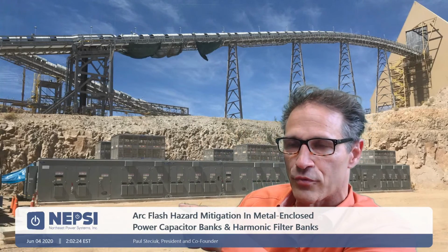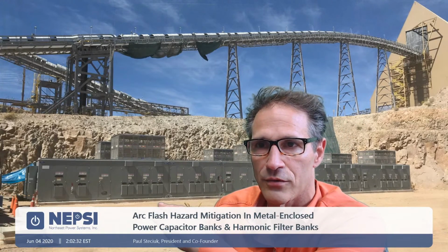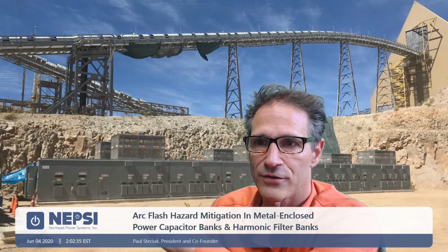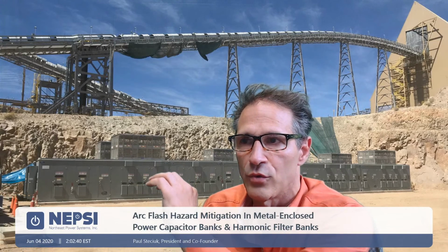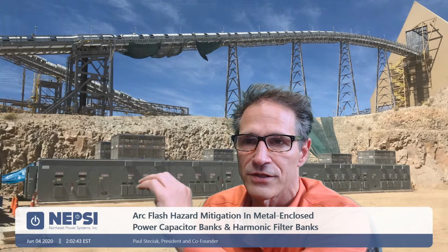So today we are going to be talking about arc flash hazard mitigation as it applies to metal enclosed harmonic filter banks and metal enclosed capacitor banks at the medium voltage level, 2.4 kV through 38 kV. Sitting behind me on our backdrop, this is new, we have a project that we supplied to Toquepala mine site in Peru. And one thing to always think about when you're specifying metal enclosed systems is arc flash hazard mitigation, because you have a lot of people that will be walking in front of this equipment, and arc flash hazard is something that should be considered.